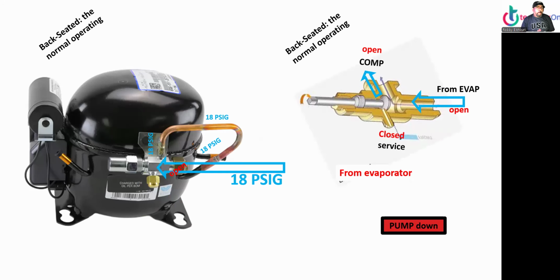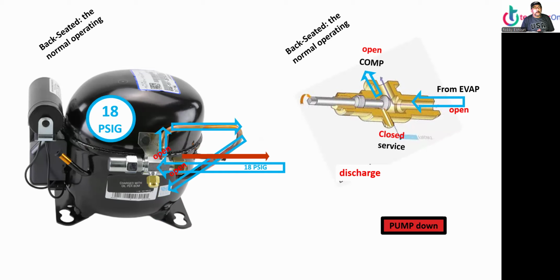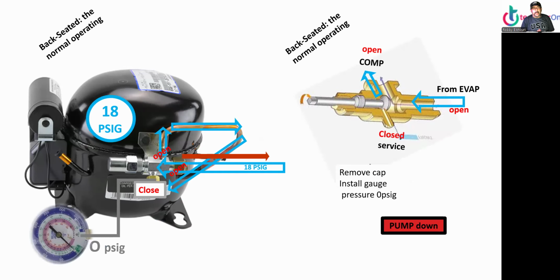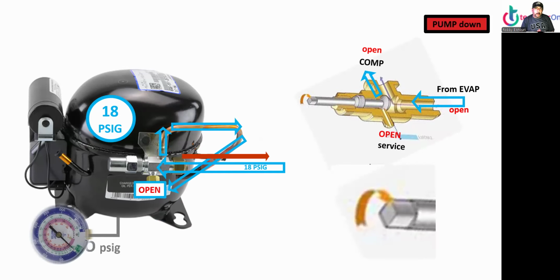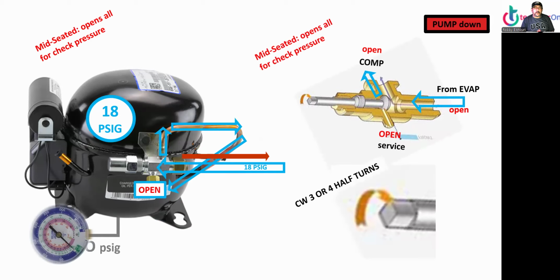So now, backseat normal operation. Right, it's open on both sides. Pressure on the evaporator 18, pressure going to the valve 18, 18, 18, and discharge. And we have the gauges, but it's 0 psig because it's still closed, but still in the backseat position. Now, to pump down, mid-seat position, we turn it clockwise 3 or 4 turns, just a little bit to get the pressure. Now we open it. We should get some kind of pressure now on the gauges. There we go. Now we have pressure on the gauges, 18 psig, same as system pressure.